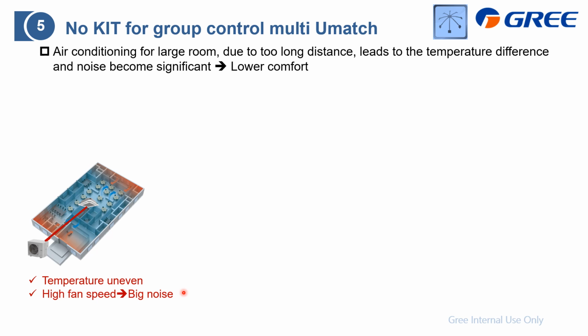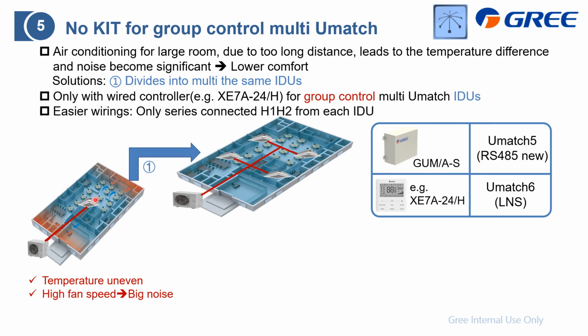And our solution is that first we can divide this one into small size or small capacity indoor units, and also connect them with the same outdoor unit. For this part, for our last generation, which is UMatch 5, we need to apply this one. It's an adapter which synchronizes control of all the connected indoor units. But for the UMatch 6 or UMatch LNS, we just need to apply this wired controller. Then we can control all the indoor units with one touch. Actually, it is a group control.